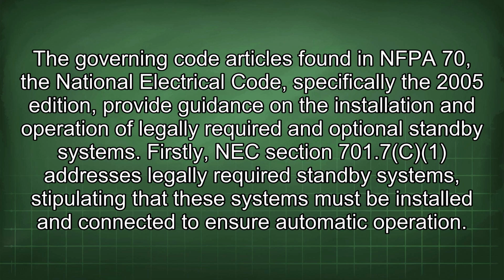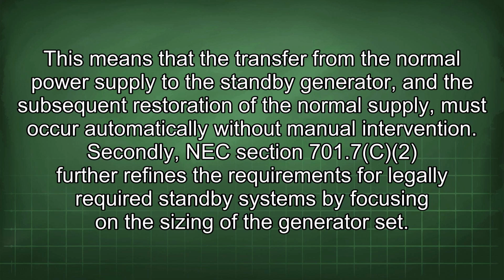Firstly, NEC Section 701.7 addresses legally required standby systems, stipulating that these systems must be installed and connected to ensure automatic operation. This means that the transfer from the normal power supply to the standby generator and the subsequent restoration of the normal supply must occur automatically without manual intervention.